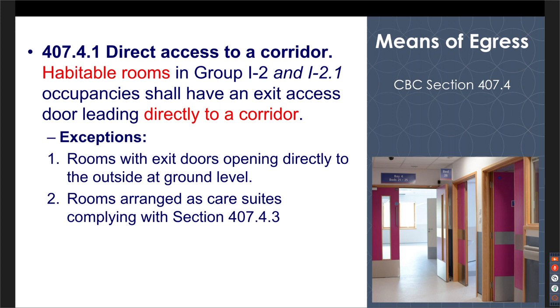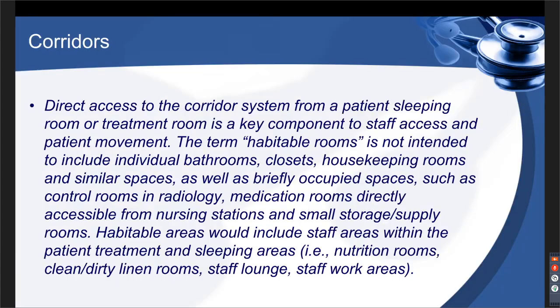What is a habitable room, Nancy? What the heck does that mean? We have a CAN for that too, and it'll explain it as well. But habitable rooms, it's not intended to include individual bathrooms. The public bathrooms are different, but it's not intended to include individual bathrooms, closets, the housekeeping rooms or spaces like that, as well as the briefly occupied spaces like a control room in radiology, or the medication room directly accessible from the nurse's station, etc. So there are certain rooms like that that you don't have to look at as habitable.